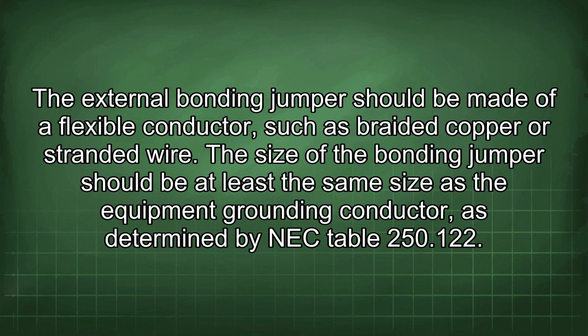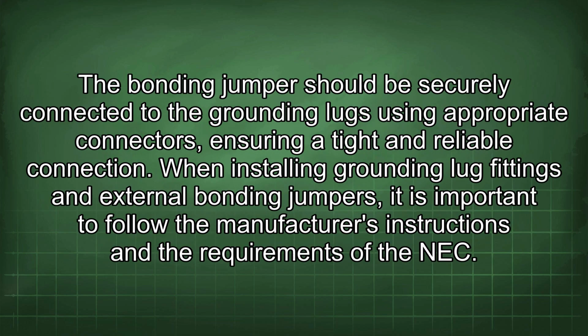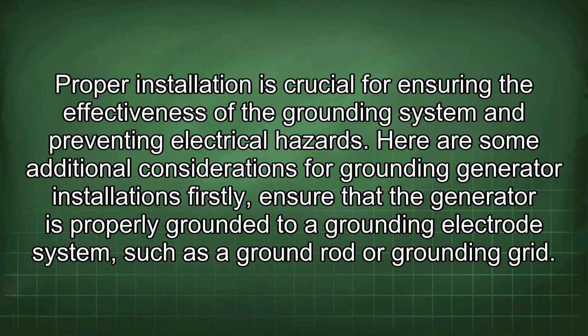The size of the bonding jumper should be at least the same size as the equipment grounding conductor, as determined by NEC Table 250.122. The bonding jumper should be securely connected to the grounding lugs using appropriate connectors, ensuring a tight and reliable connection. When installing grounding lug fittings and external bonding jumpers, it is important to follow the manufacturer's instructions and the requirements of the NEC. Proper installation is crucial for ensuring the effectiveness of the grounding system and preventing electrical hazards.